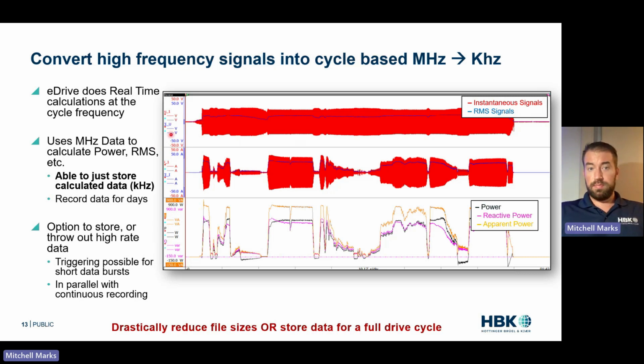If you don't want to store all that, a tool like eDrive uses some data reduction techniques where every half cycle we're calculating that value, and then we're storing that value, and then we can throw out all of the other data. So you can store just those calculated results and reduce your data file size from gigabytes to megabytes. So it's a really powerful tool, and that's because we calculate everything in real time. We're calculating everything in hardware, and then we're just storing those results, so you're not filling your hard drive up. By doing those cycle-based calculations, all of that megahertz is going into that calculation, and then we're not storing it.